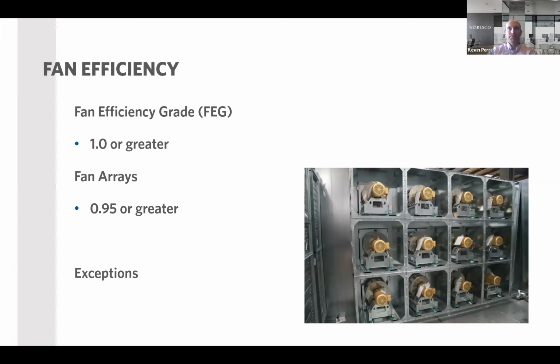Fan efficiencies, you know, nothing crazy here. It used to be 0.67 or greater for fan efficiency grade. Now it's 1.0 or greater. And they also added a section for fan arrays. So if you have a fan array, your fan efficiency grade has to be 0.95 or greater. And there is a slew of exceptions in here. I think there's like a dozen of them. So just know that you could be exempt on some of these.